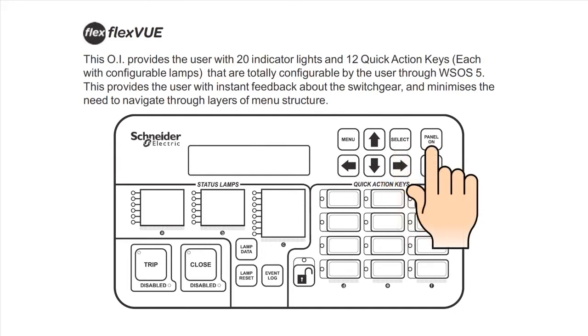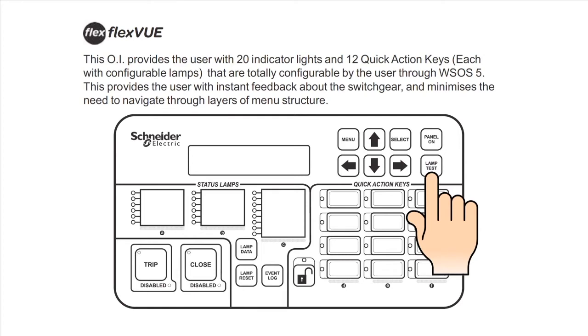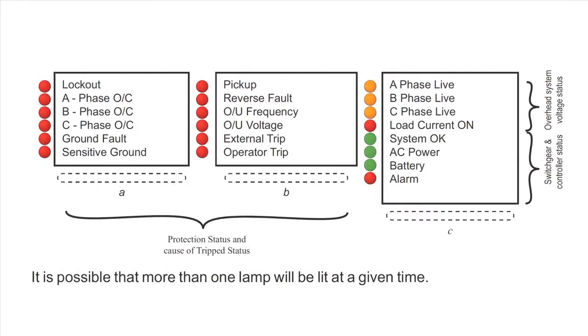Panel on key turns the panel on or off. An optional door switch is available to turn the panel on when an operator opens the door and off when the door is closed. If the controller is fitted with this option, the button can be used to turn the panel off or on while the door is open. Closing the door turns the panel off. Lamp test key tests all lamps on the panel. The purpose is to alert the user of any lamps or colors that may not be working correctly. The test simultaneously cycles all lamps through red, orange, and green.